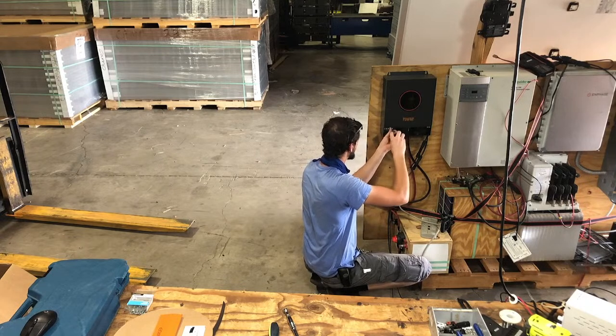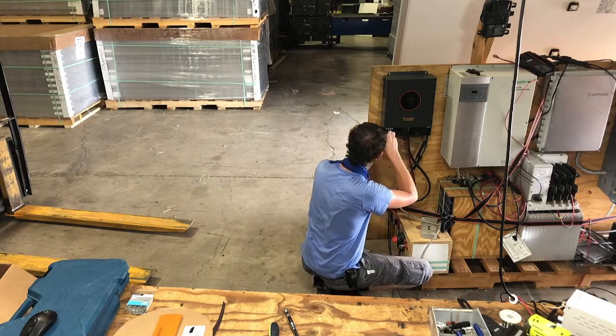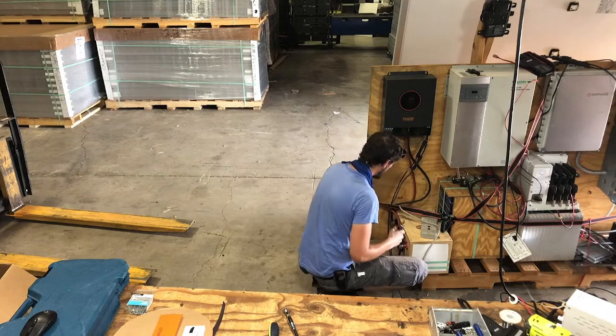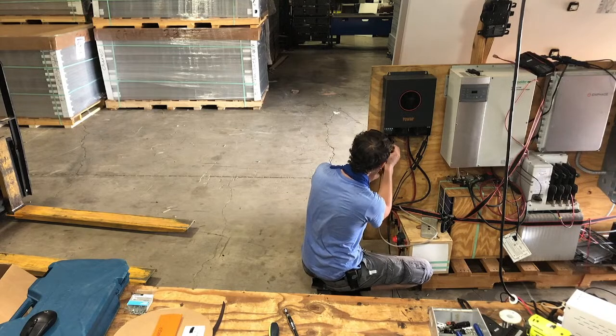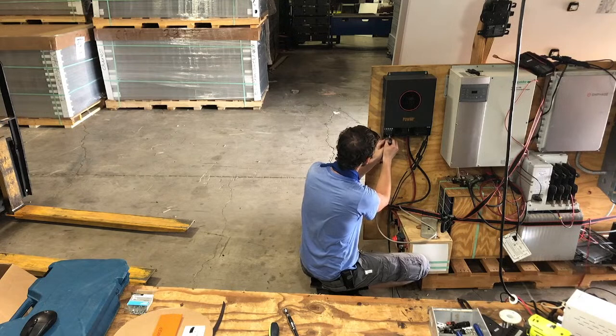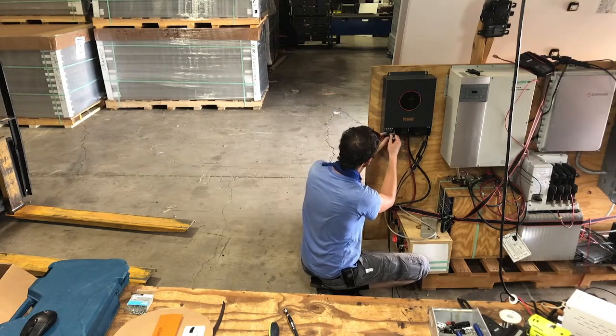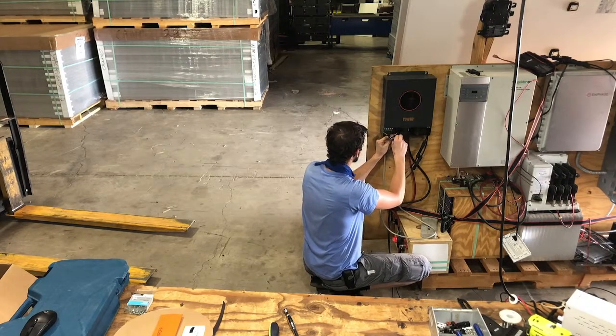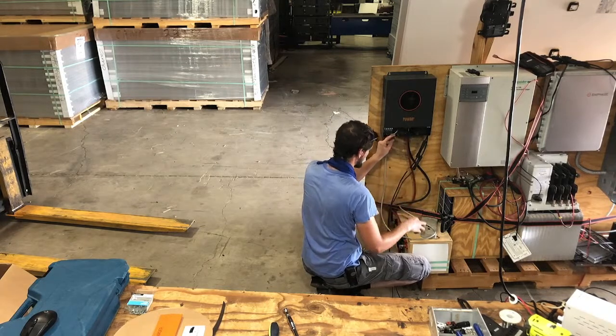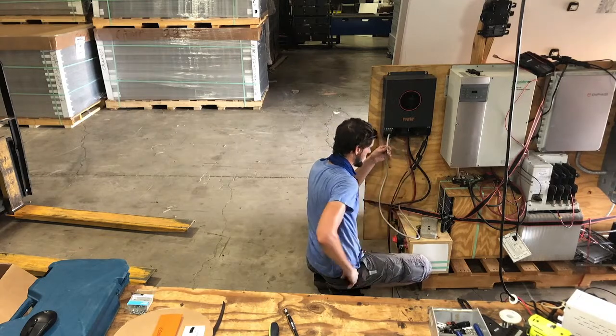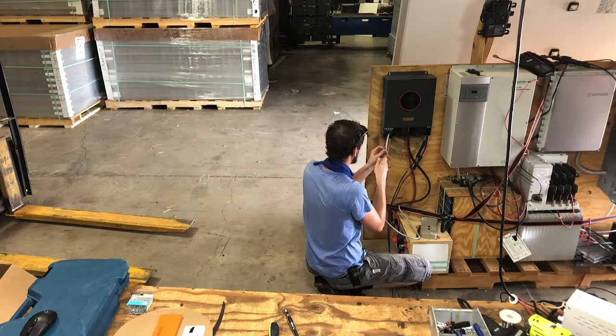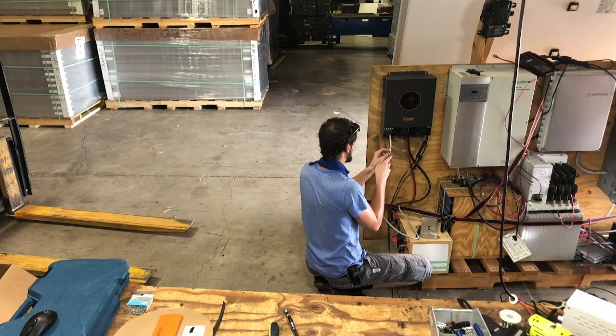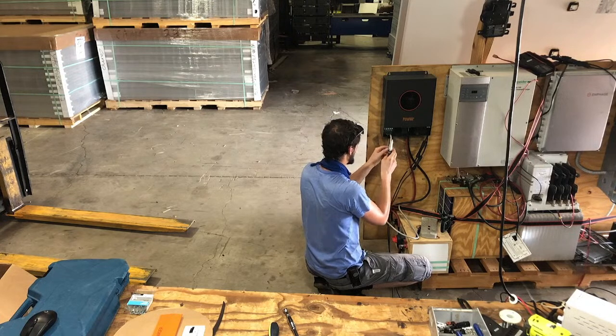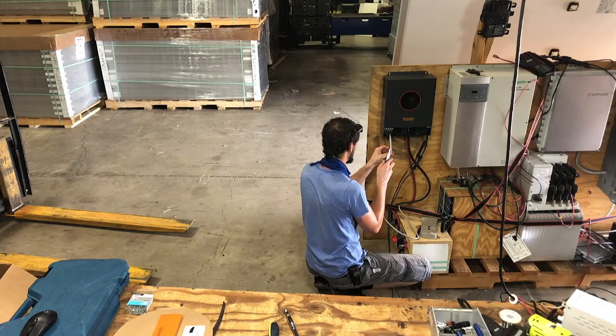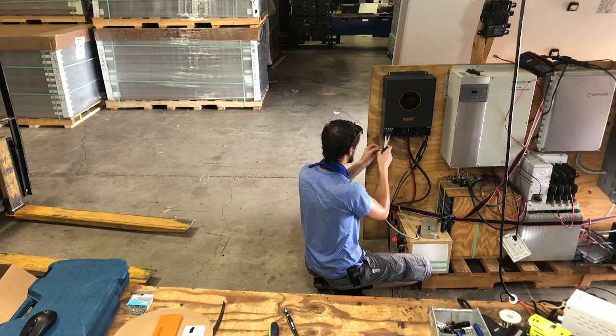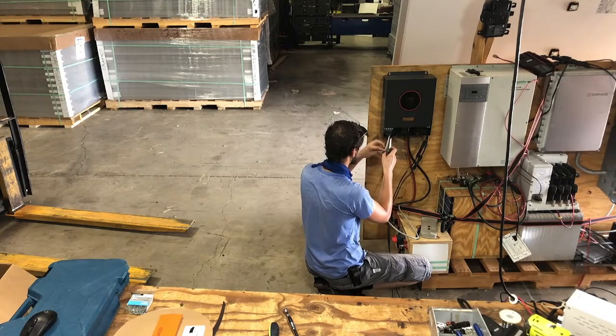Something I'm probably overlooking here, but something I really wish all these all-in-one manufacturers would do is include a relay inside the unit that would bond or connect neutral and ground, so that in off-grid mode, no generator, no grid, they're connected inside the inverter. Then if the grid or a generator ever comes on, it allows the grid or generator to do the bonding. As it is, most of them just overlook it, like they're not going to deal with that, so they end up not being bonded. Then you either have to figure out a way to do a relay yourself, or make sure you don't have GFCIs, because if you leave them unbonded, you end up with voltage or potential between neutral and ground.